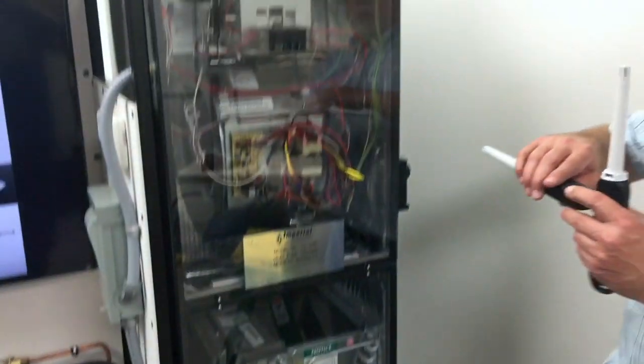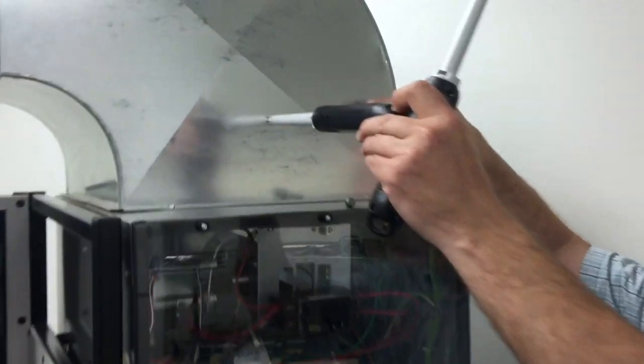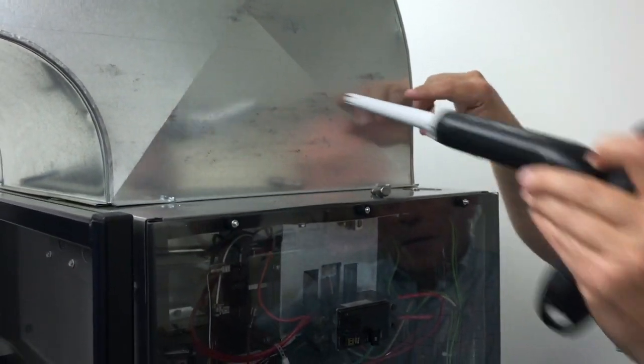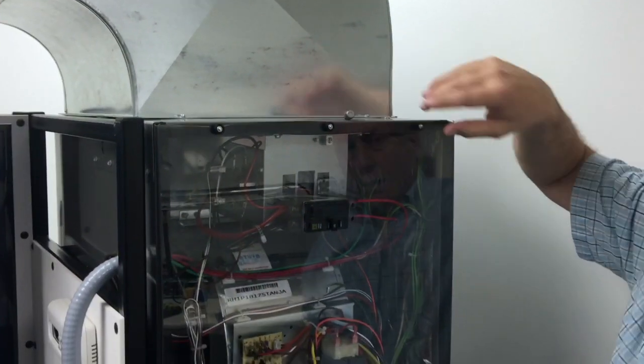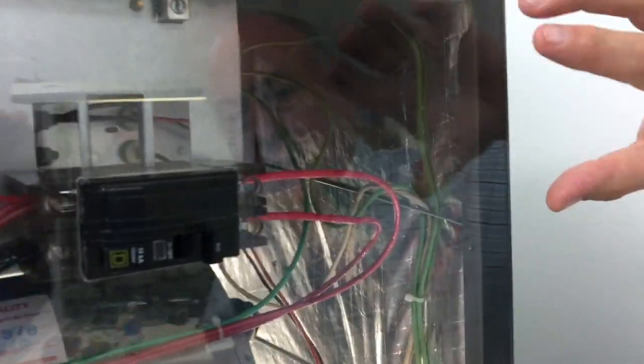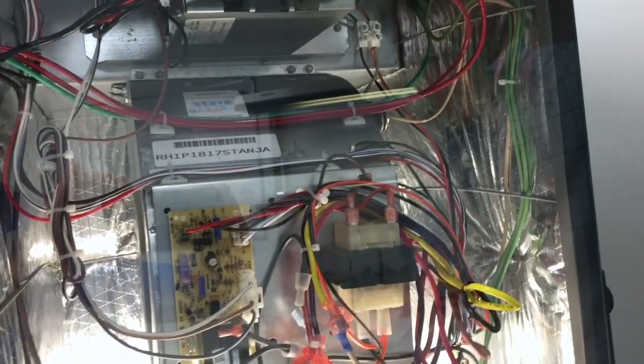The other place we don't want to be is up here in the front of the ductwork right here, right above the fan housing, because there's a dead spot right here. If you look inside this cabinet and we flip the light on so you can see a little bit in the back, that ductwork goes quite a ways back in there and it's on a dead spot right here.